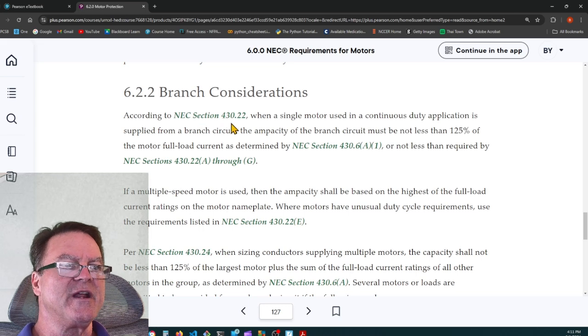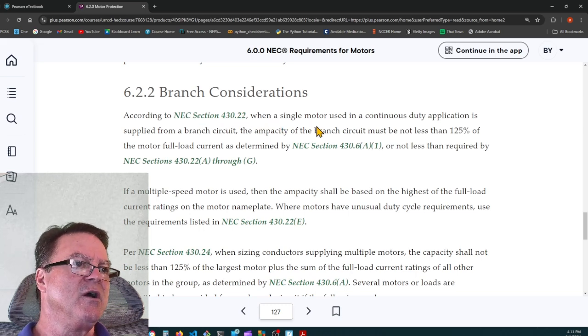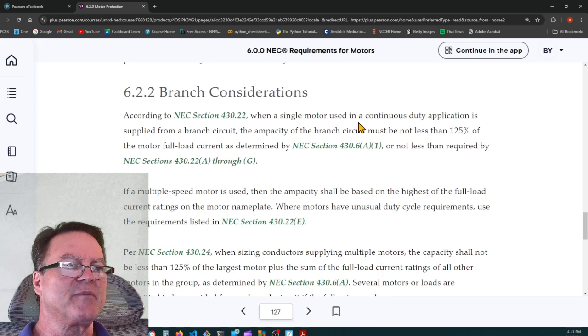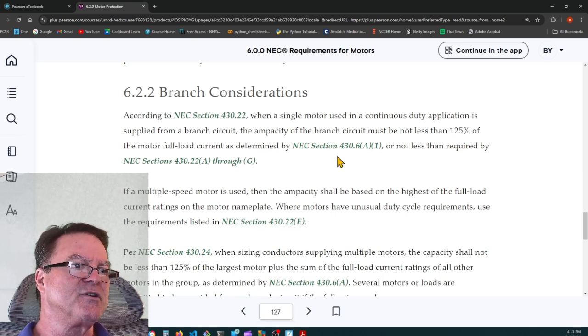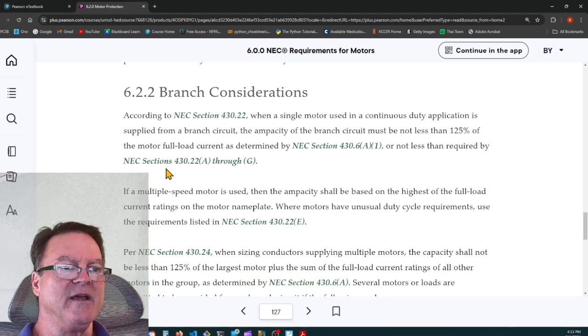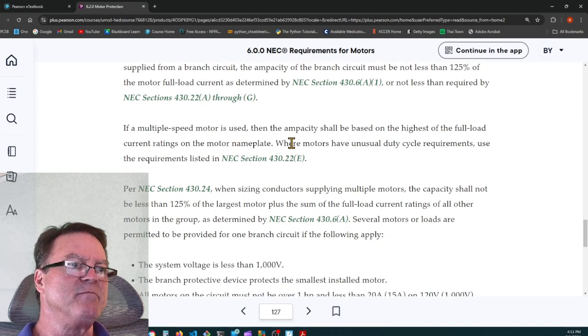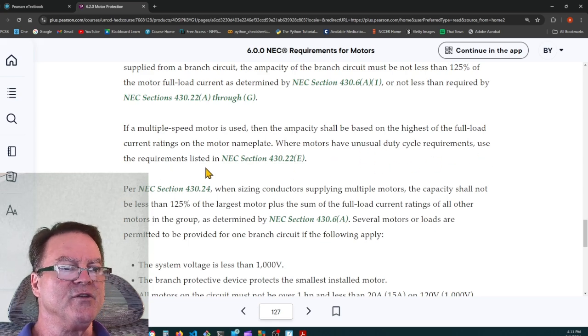Branch considerations. According to NEC section 430.22, when a single motor used in a continuous duty application is supplied from a branch circuit, the ampacity of the branch circuit must be not less than 125% of the motor full load current as determined by NEC section 430.6A1, or not less than required by NEC sections 430.22A through G. If a multiple speed motor is used, then the ampacity shall be based on the highest of the full load current ratings on the motor nameplate. Where motors have unusual duty cycle requirements, use the requirements listed in section 430.22E.